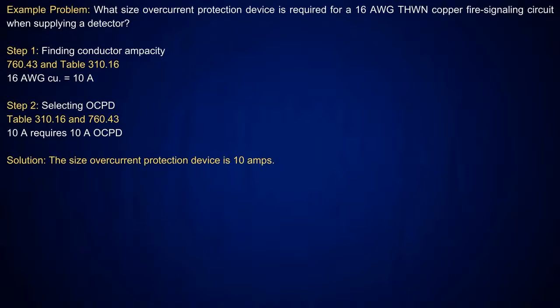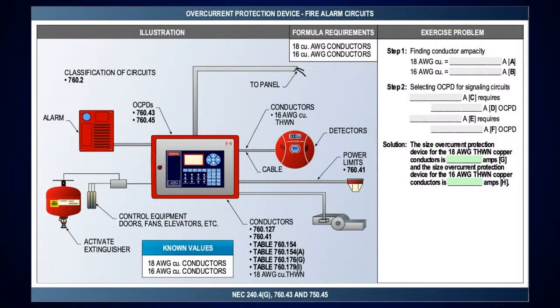This is actually given to you when you go over and look at 760.43, but we're just sort of proving a couple of things here. When you look at table 310.16, you pick up the 75 degree C column, it tells you number 16 is good for what? Number 10. Therefore, you look at 760.43, it matches up. You need a 10 amp overcurrent protection device. Pretty simple.